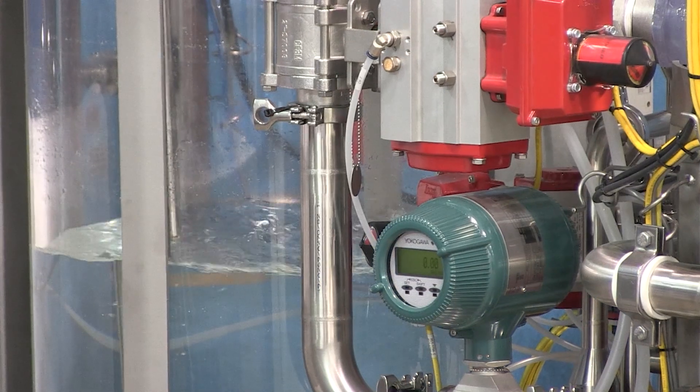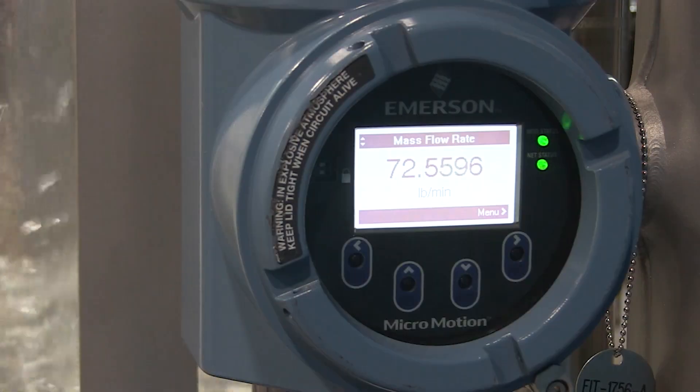HART stands for Highway Addressable Remote Transducer. It is a digital sine wave that exists over top of an existing 4 to 20 milliamp signal. HART is the most common protocol in instrumentation with over 40 million HART-enabled devices installed worldwide.